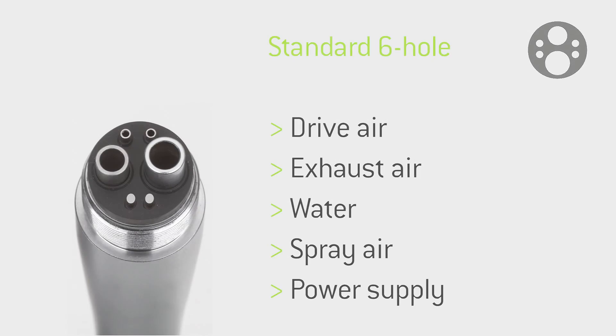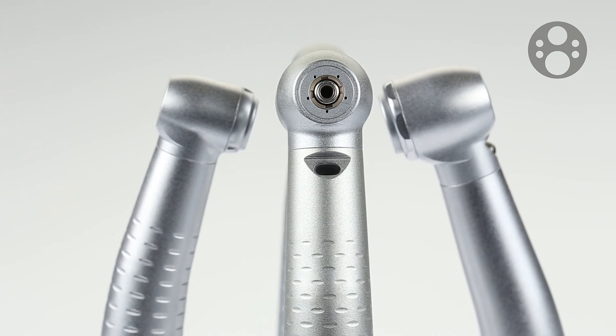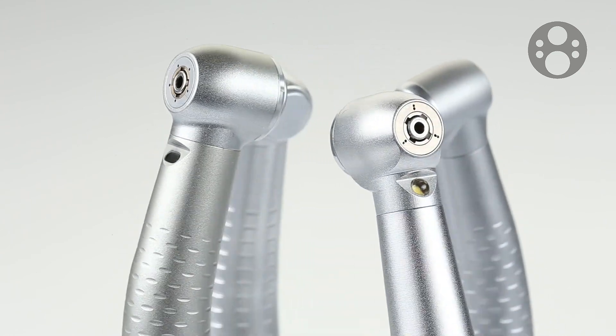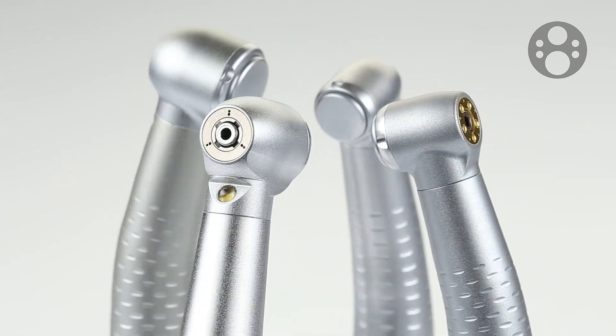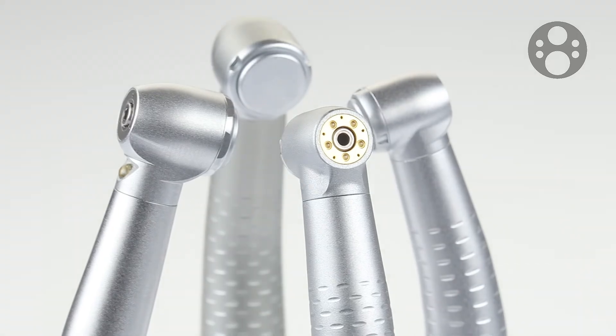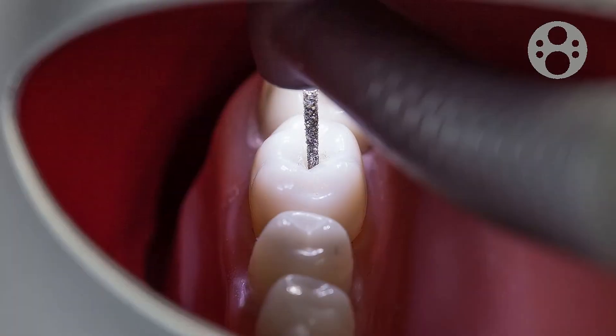The standard six-hole connection has, in addition to the standard four-hole connection, two electrical contacts through which a light can be operated. With this energy, both halogen bulbs and modern LED systems can be operated, allowing optimal lighting of the treatment area.